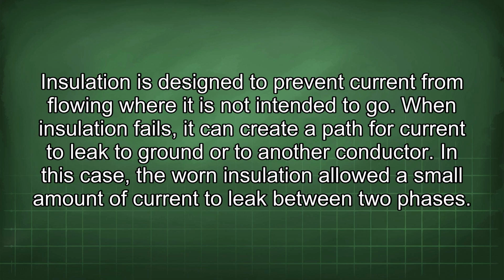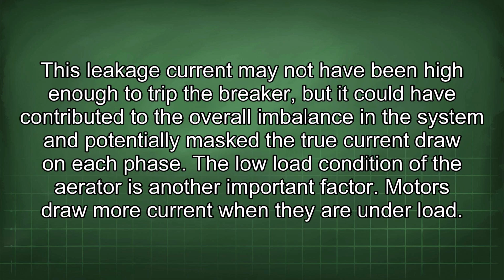Now let's consider the partial insulation failure in the power cable. Insulation is designed to prevent current from flowing where it is not intended to go. When insulation fails, it can create a path for current to leak to ground or to another conductor. In this case, the worn insulation allowed a small amount of current to leak between 2 phases. This leakage current may not have been high enough to trip the breaker, but it could have contributed to the overall imbalance in the system and potentially masked the true current draw on each phase.